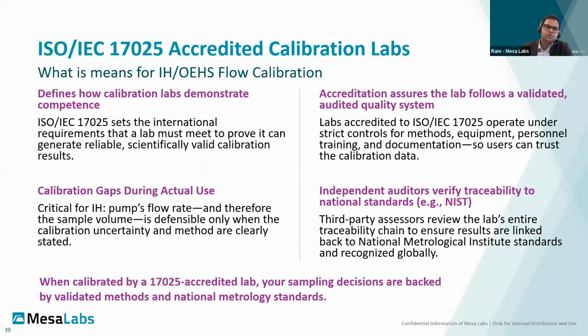Next slide, please. So now that we've established why working with OEMs is critical, the next question is how do you ensure that the calibration itself is credible and defensible? This is where ISO 17025 accreditation becomes important. An accredited lab will have demonstrated through independent audit that it operates under a validated quality system. This includes controlled procedures, trained personnel, documentation of measurement uncertainty, and full traceability to national standards. For IH and OEHS applications, this directly impacts confidence in flow data, sample volume, and ultimately exposure results. These are only as reliable as the calibrations behind them. So once again, the take-home message is work with OEMs, and OEMs who are accredited to do the service.